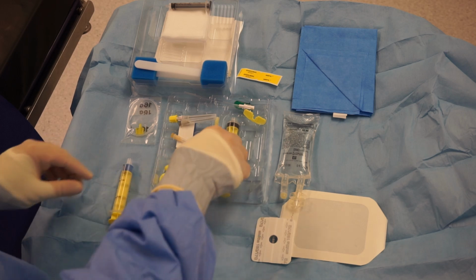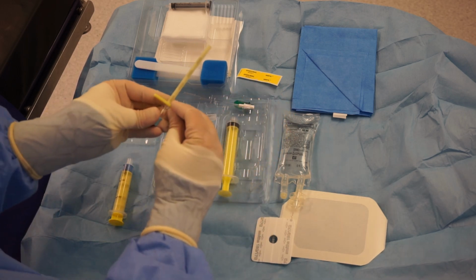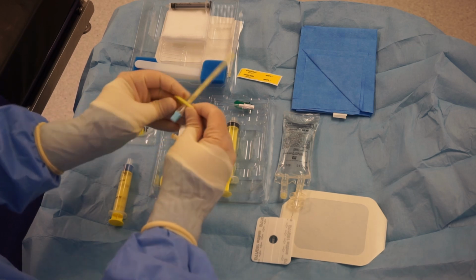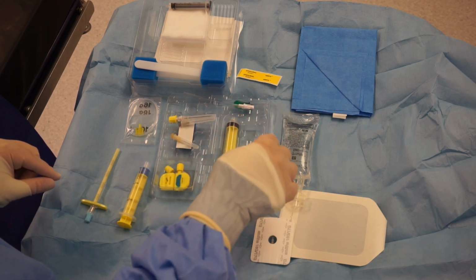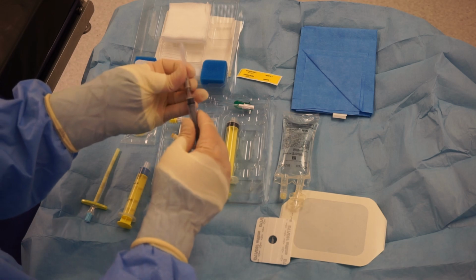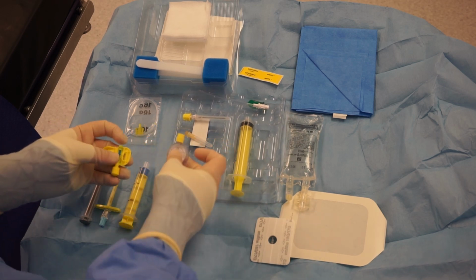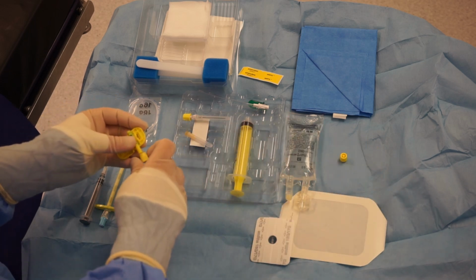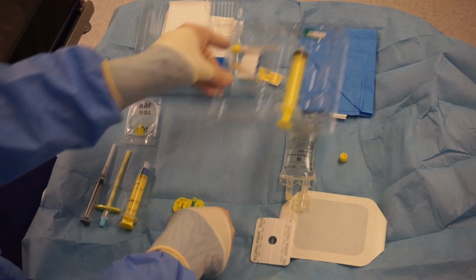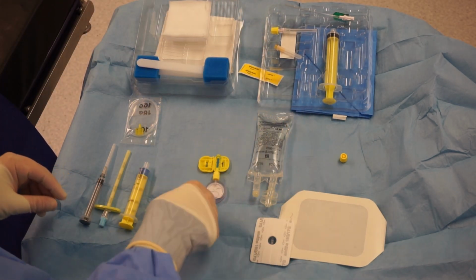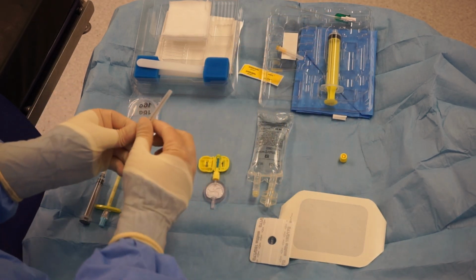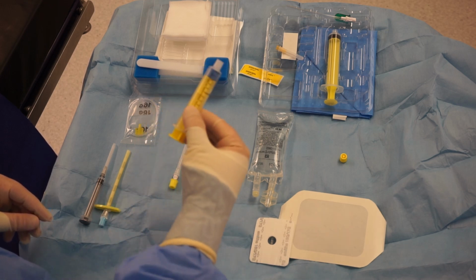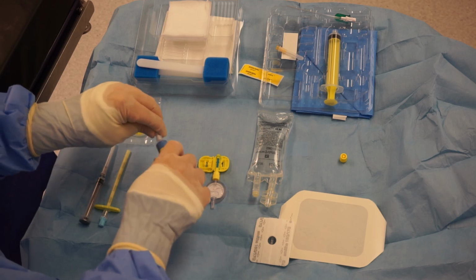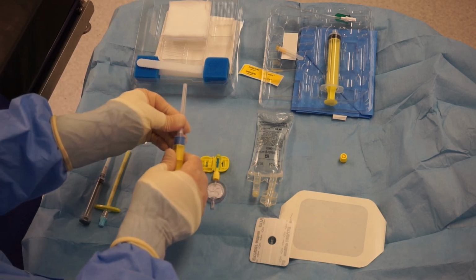Note the use of yellow plastic on the plunger of the loss of resistance device. This identifies that it is an NRFit connector. You will need to clip the wings onto the Tuohy needle as shown. The grey 3ml syringe is not NRFit, but a Luer connection. It is designed to be used here for the local anaesthetic. Attach the white filter to the yellow locket, ensuring you retain the yellow cap for the end of the procedure. The use of yellow caps, as seen on this needle, are also used to denote an NRFit connection. As you see, it will attach to the loss of resistance device easily. If you try this with a grey needle, you will find them incompatible.